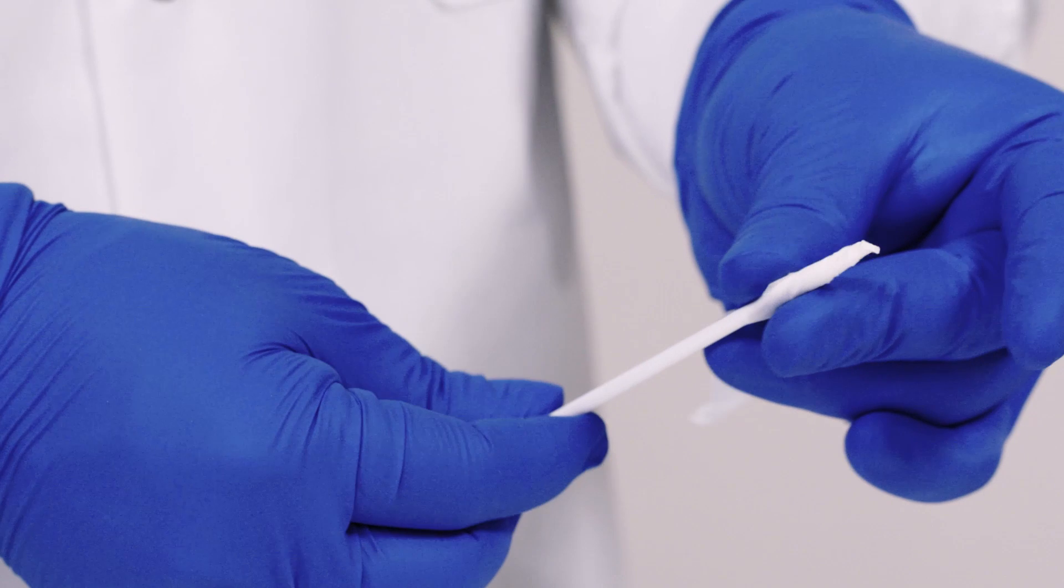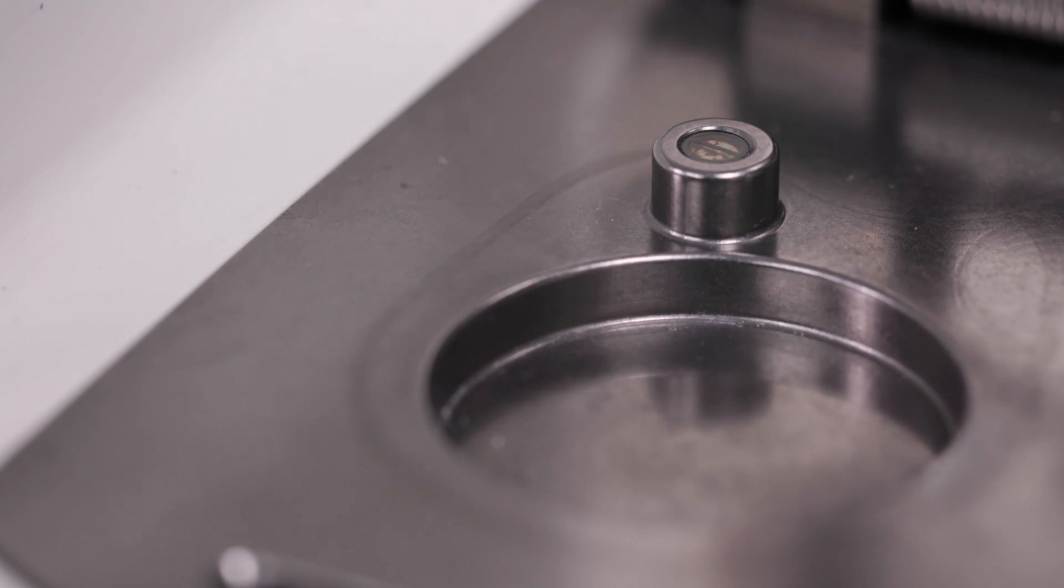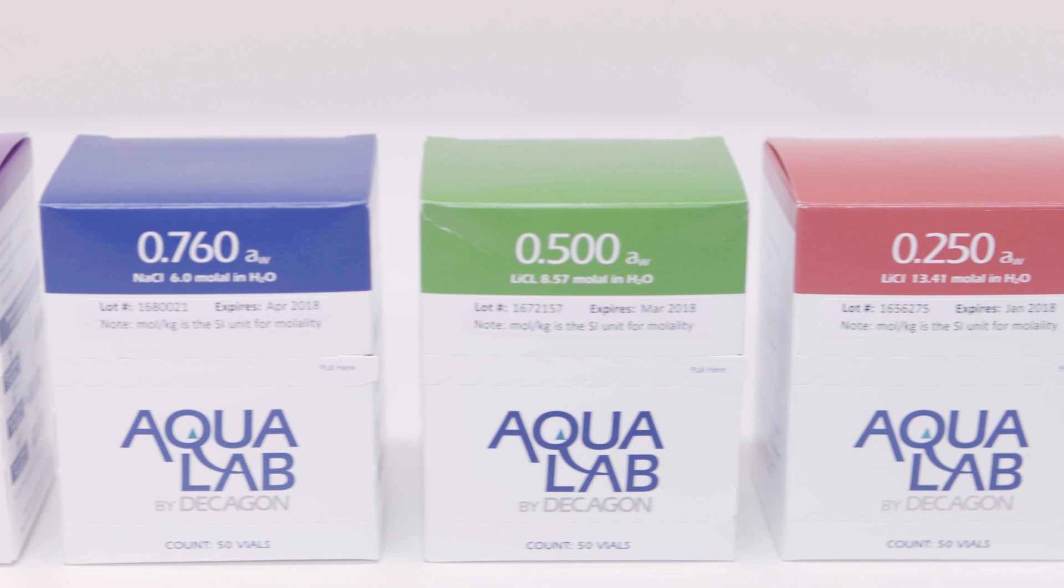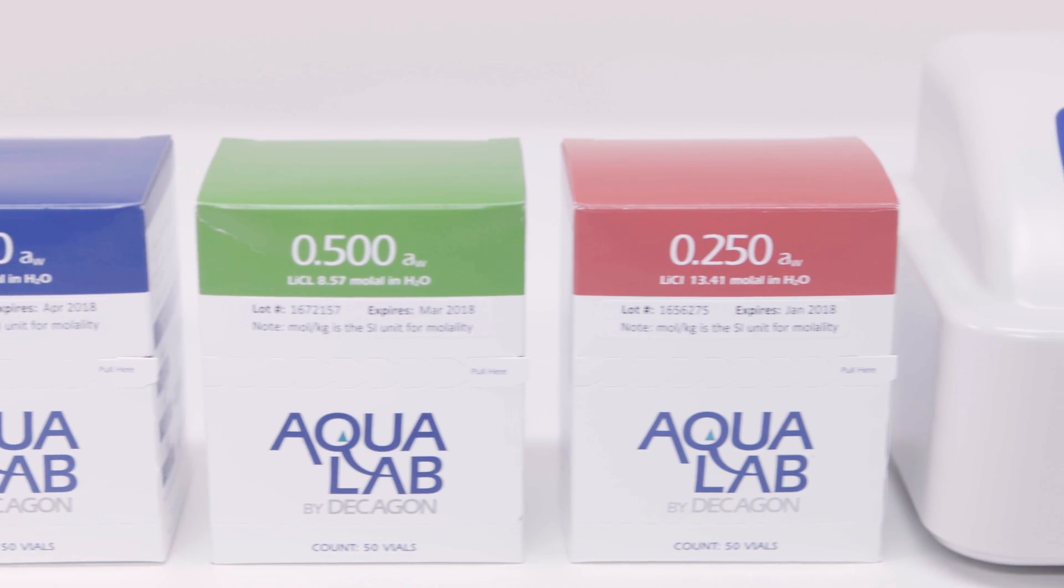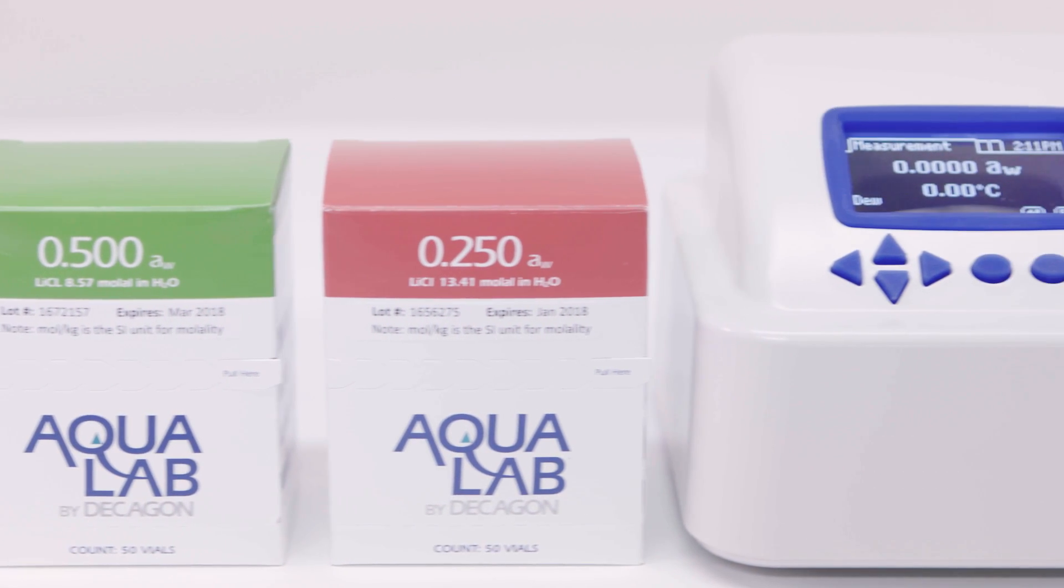Once the cleaning process is complete, let the sample chamber dry for about five minutes while you prepare your water activity standards for verification. When your instrument reads in spec, you have finished cleaning your instrument.